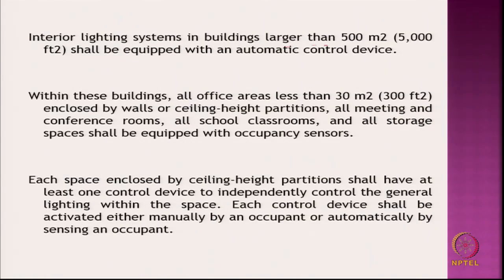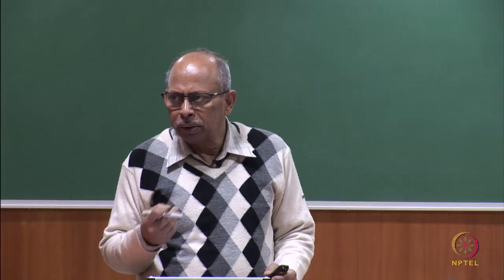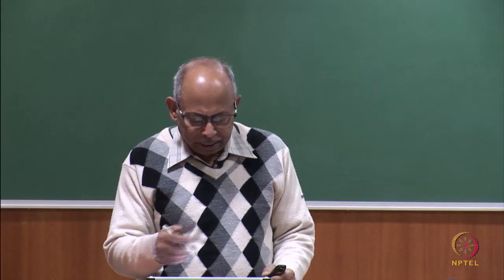The interior lighting system of a building larger than 500 meter square shall be equipped with an automatic control device. So, when you require it, you put it on, otherwise no. Within the building, office areas less than 30 meter square enclosed by walls or ceiling height partitions, and meeting or conference rooms, etc., shall be equipped with occupancy sensors. That means as you enter, the lights come on, and as soon as one is out, they go off. So, it is an intelligent system of sorts. Essentially, they could be infrared sensing. So, if somebody comes in, it senses and the lights turn on.